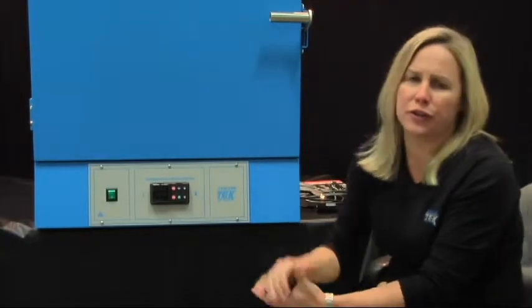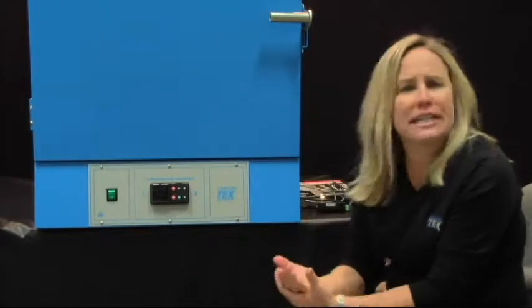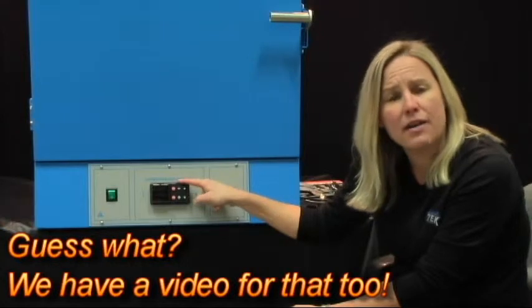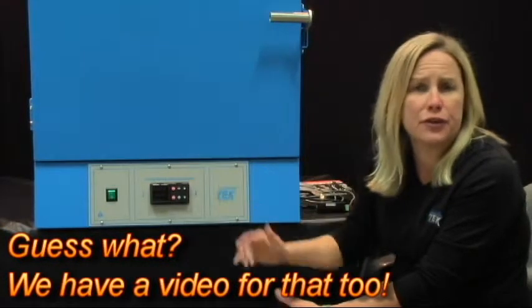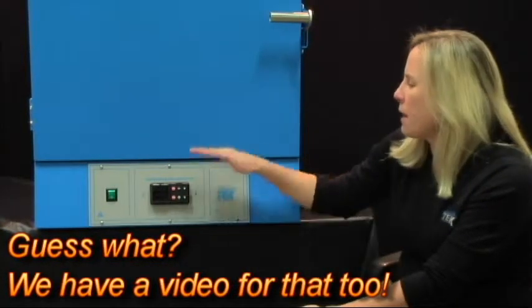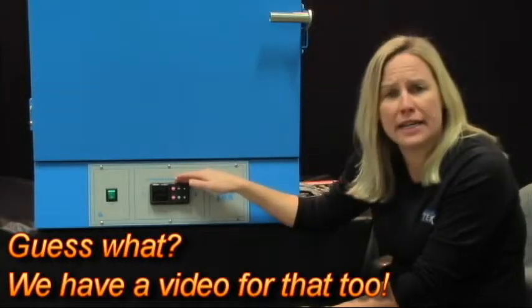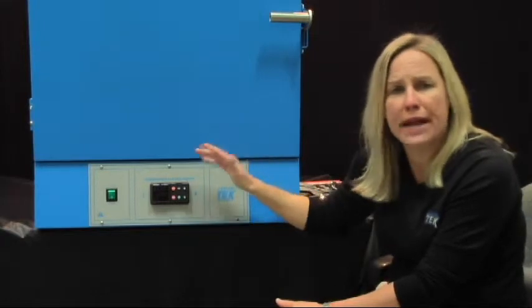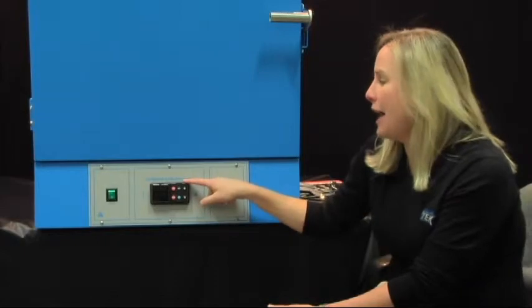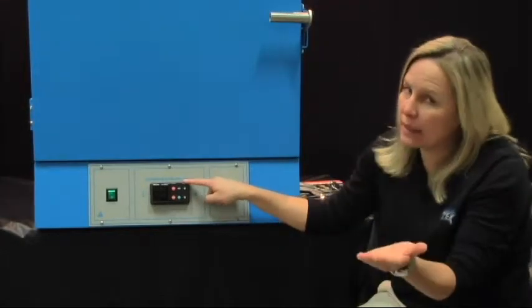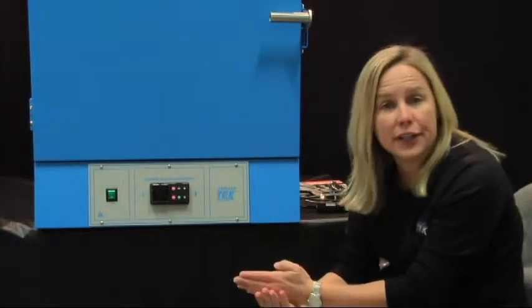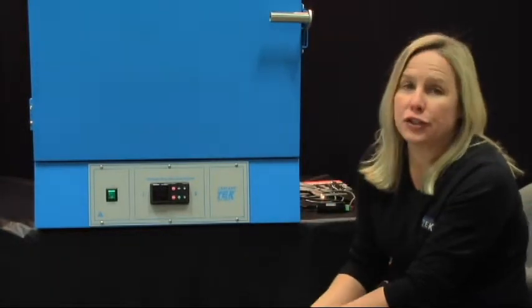So, if it's destroyed at 200 degrees C, but you need to bring it to 150 degrees C, set the over-temp limit on this controller to, say, 175. It's fully independent FM rated over-temp protection. So, if for some crazy random reason you have a temperature runaway condition, the high-temp limit control, or over-temp protection, will kick in and it will actually cut power to the heaters. That's a great feature to have.